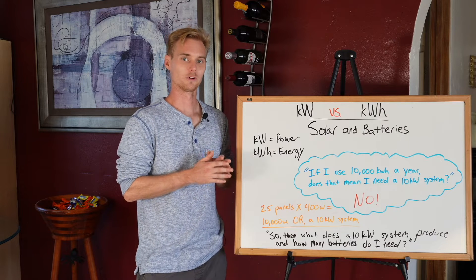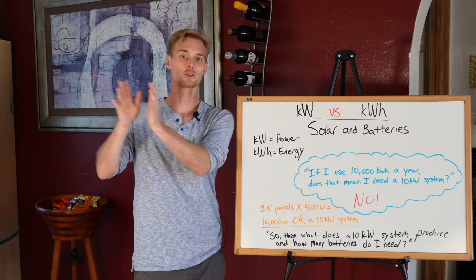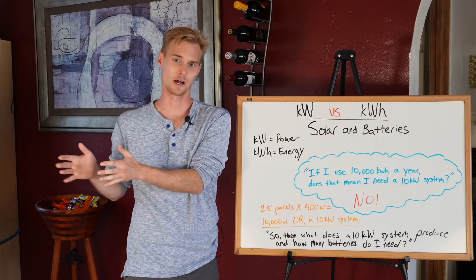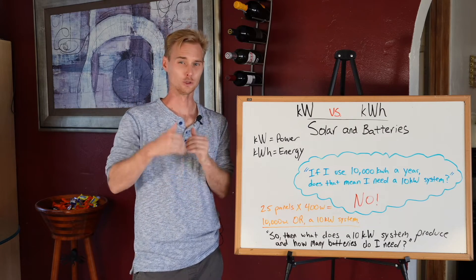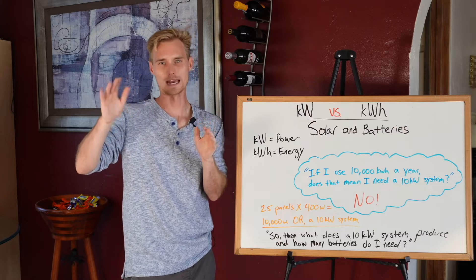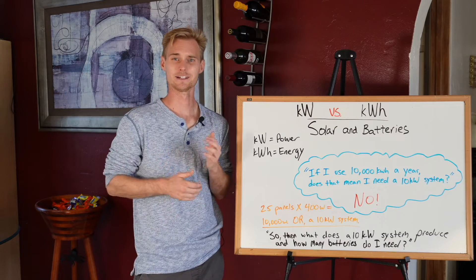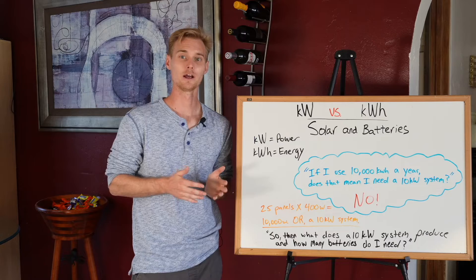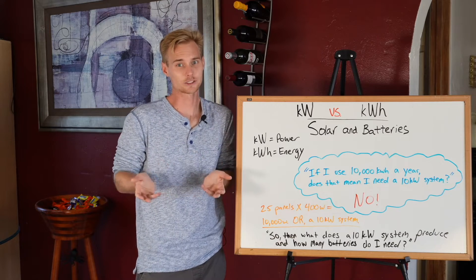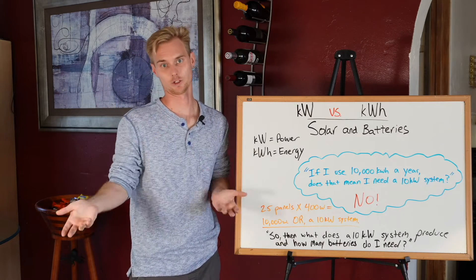The kilowatt hour calculation works the same way but over 365 days. The math won't come out to where a 10 kilowatt system magically produces 10,000 kilowatt hours. In North America, depending on where you are, the ratio of kilowatts to kilowatt hour production is usually around 1.4 to 1.8. A 10 kilowatt system in Southern California may produce around 16,000 to 18,000 kilowatt hours through the year. So if you're using 10,000 kilowatt hours, you probably need something closer to a six or seven kilowatt system.